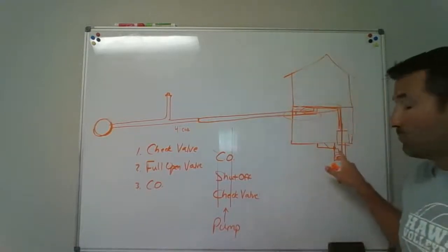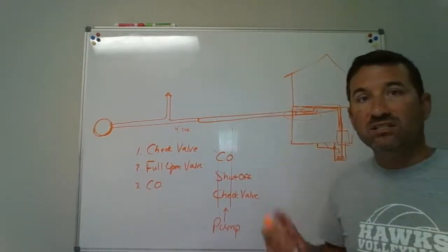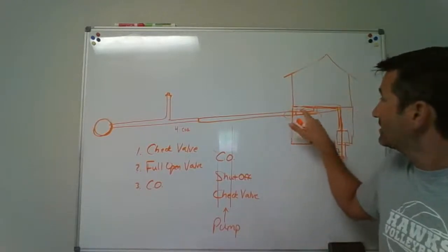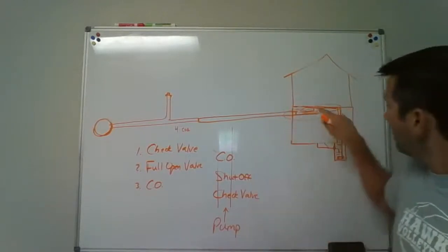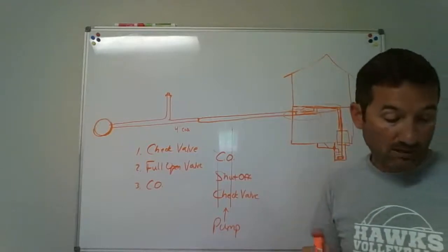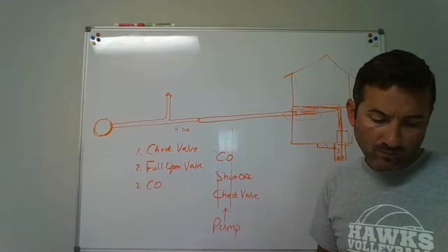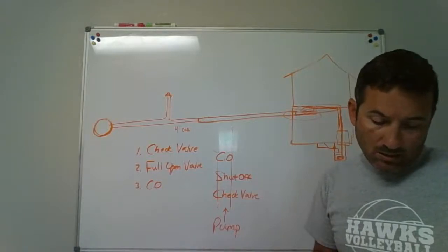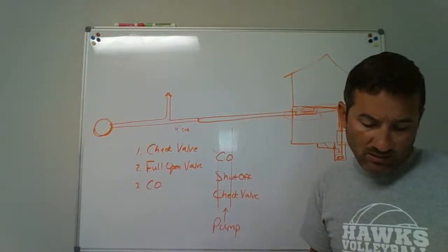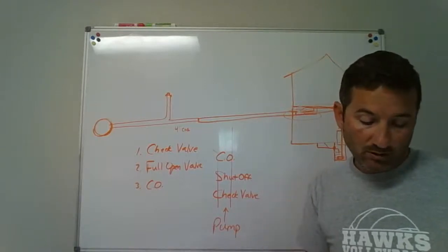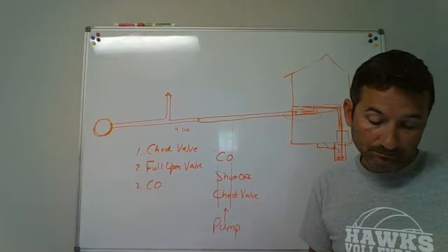It can handle the pressure. They're going to say, well, we're pumping it out, so it's going to be under pressure as it gets pumped. So we want all the fittings and the line until it ties into your existing to be pressure rated PVC piping. Let's see, it says the material is excluding cell core product. So no, can't use them. Okay.